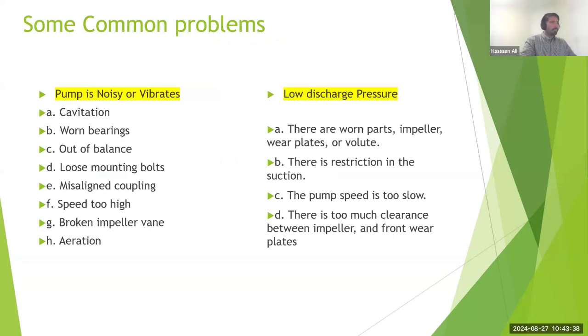Thank you very much. So the common problems which I have seen in the industry, based on my 14, 15 years of experience with these pumps, is the vibration. Vibration is one of the common things that we see because it is very evident very quickly.